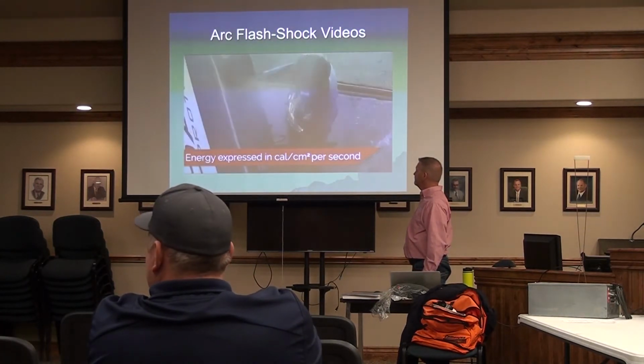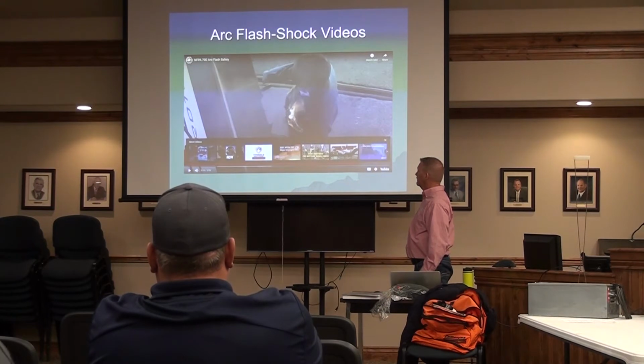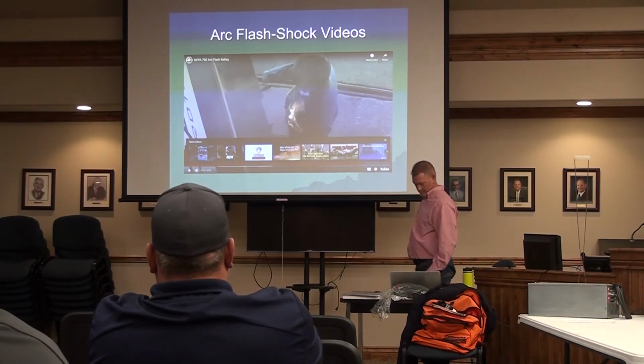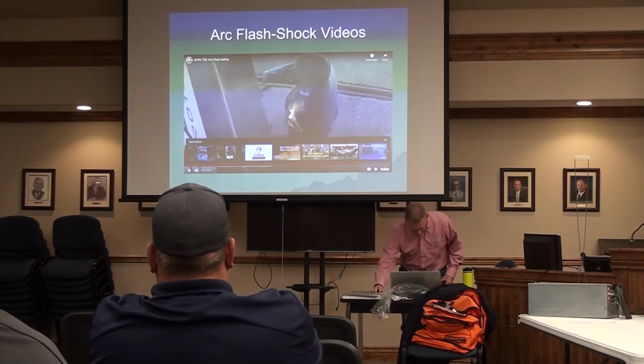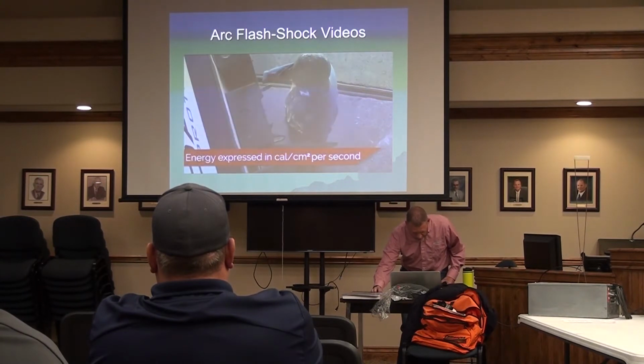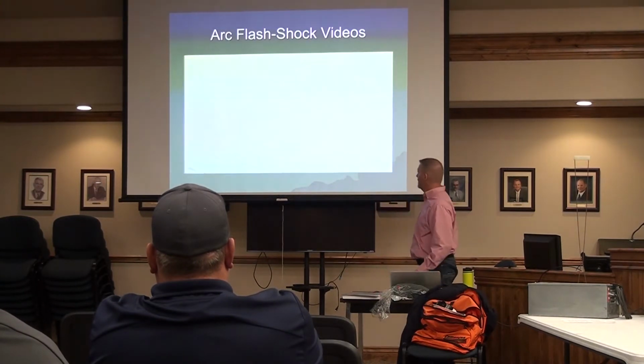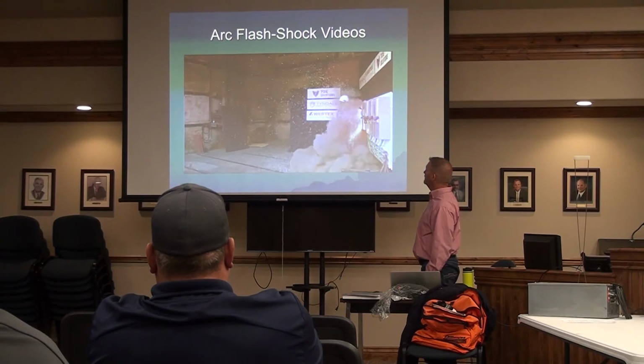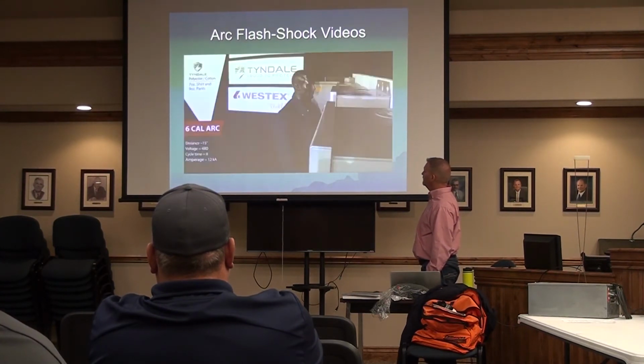When we talk about arc energy, we measure it in calories per centimeter squared per second. A typical arc flash can release energy anywhere from a few calories up to 20, and exposures between 20 and 40 calories are not at all uncommon.